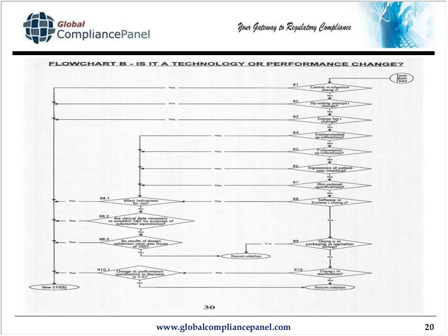In situations like this, either we're changing our sterilization parameters, or we're keeping our parameters exactly the same, but we're changing sterilizers, we're changing the facility, or in the most obvious case, we're changing our sterilization mechanism. We're changing from ETO to gamma, for example.